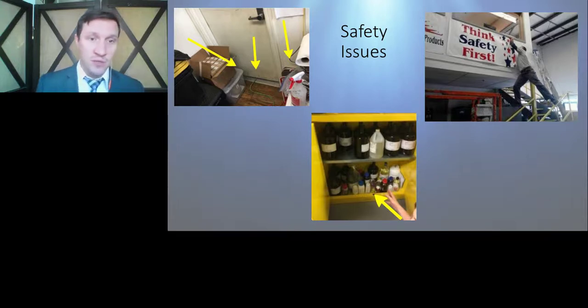The other issue in the middle is that there's an extension cord that's running on the floor and under the door. So number one, that extension cord should not be permanently installed. Extension cords are for temporary use. Number two, it's a tripping hazard because it's running across the doorway. And number three, that's going to wear down over time because the door is rubbing against it constantly, right?